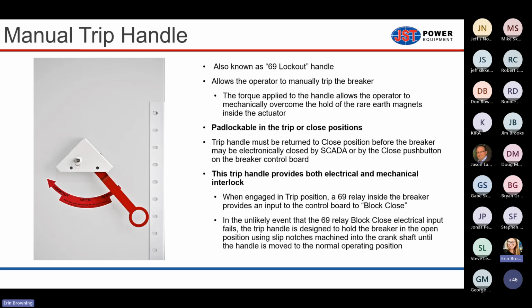reset of the breaker. You can't close the breaker with this handle, but if it's in the middle open position, it would allow someone to remotely close the breaker. And if you're working on it, you don't want anyone to be able to remotely operate it. So that's why we have a padlock and a pin lock as well; it's a secondary device to prevent you from accidentally closing the breaker or allowing someone to close it.